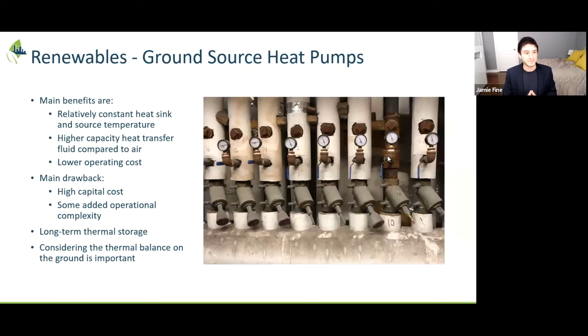Just a couple other points. When you're looking at any of these systems, there are a few important factors. Number one, what's the peak load of the building? Number two, when you look at the design month of the building, especially true for ground source heat pumps, the design month and what your part load factor is. So how much of the time is your equipment running during that coldest month of the year, or warmest month of the year. On top of that, looking at the annual balance of heat over a year, you need to consider all three of these when sizing renewable energy equipment.